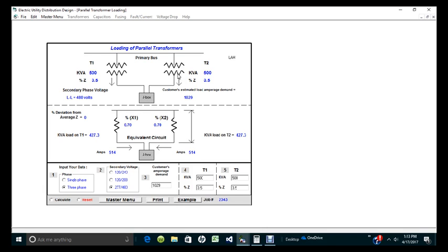Hazmat is out on the site. So consequently, you check in the yard and see what you have available to match up with the good transformer. And you come to find out, I don't have another 500 in the yard. I have a 750. It's got a different impedance. Is it going to work? Well, that's where this program comes into play.